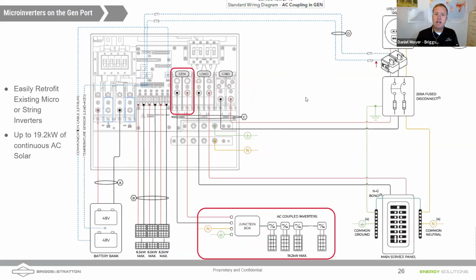So we're looking here at a single line diagram of a solar system, and we've got our grid, we've got our meter, we've got some CTs here, and these would be necessary if we wanted to measure the energy consumption of any loads that are not backed up, especially if we wanted to program an inverter to backfeed just enough to support loads here, but not send any more than what would go back out onto the grid. Grid port, right? So we've got 200 amps coming into the grid, 200 amps coming right back out of the load, down to the load center.